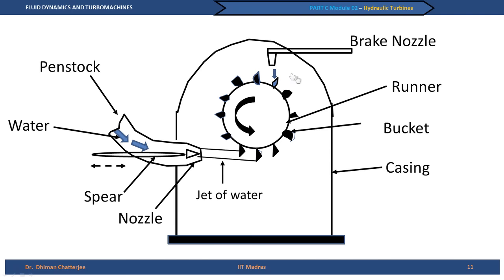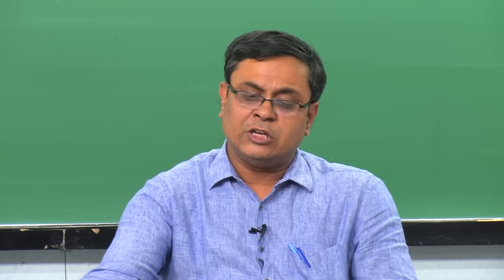These are the essential components. More often than not there is a casing surrounding the Pelton turbine. One important clarification: since the Pelton turbine is an impulse turbine, the jet of water issues out of the nozzle into open atmosphere, so the Pelton turbine essentially rotates under the impact of the jet striking the buckets in air. The casing is not required for any hydraulic purpose — it is for safety and to prevent splashing of water. In reaction turbines, by contrast, the casing is a very important component.